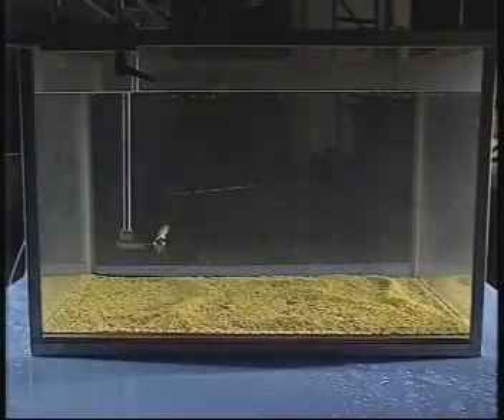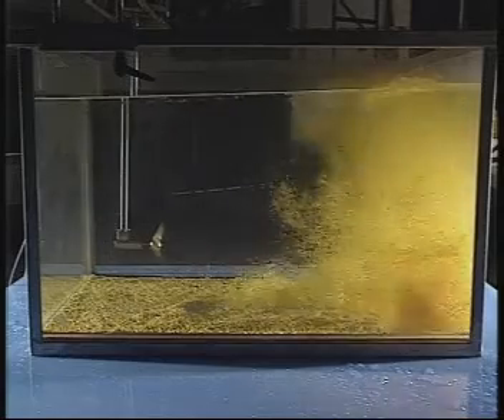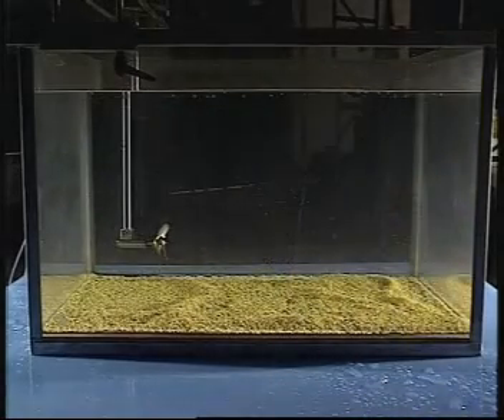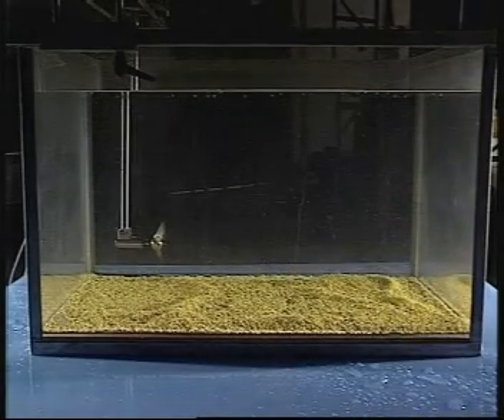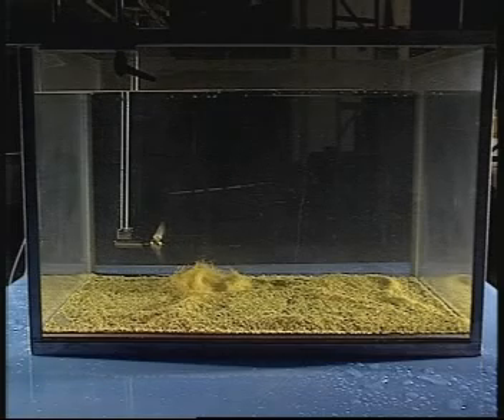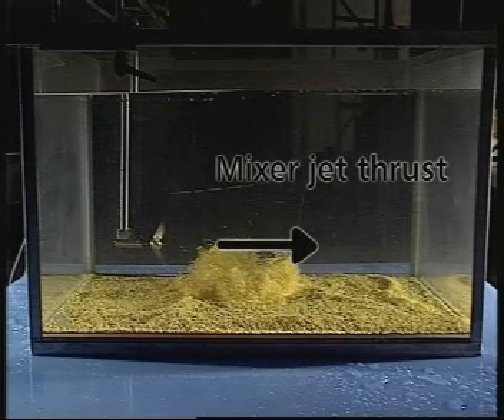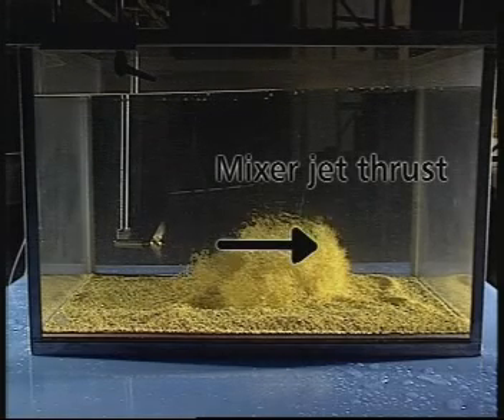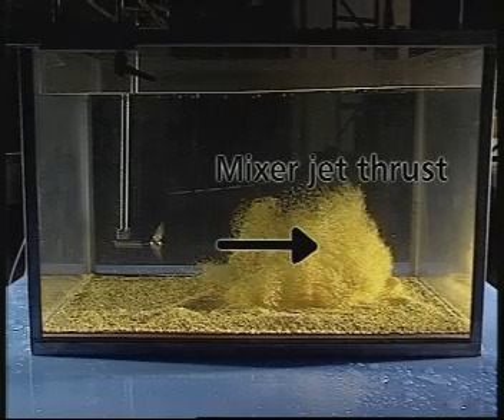The power consumption of the mixer increases proportionally to its specific gravity. A mud's specific gravity of 1.5 will increase power uptake by 1.5 times its use in water. Thrust is the force used to mix and create the jet to maintain a properly mixed drilling mud solution. The produced thrust increases proportionally to the specific gravity, which ensures that the mixing result is also independent of the specific gravity.